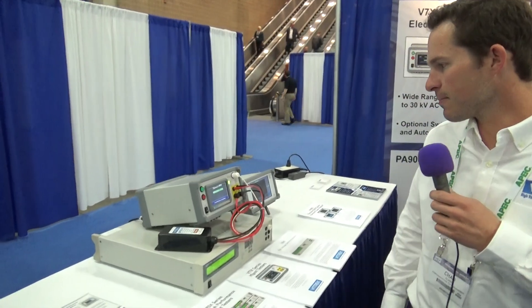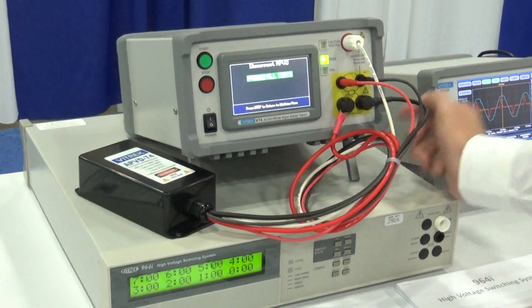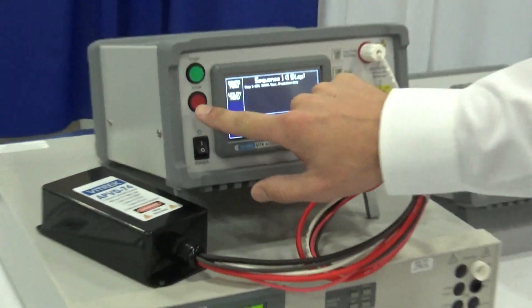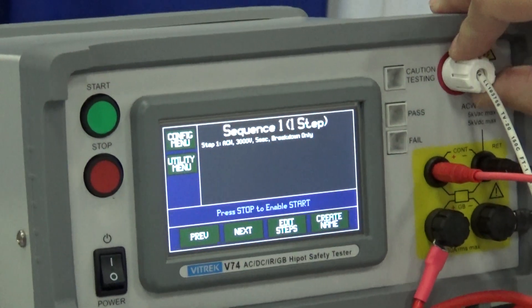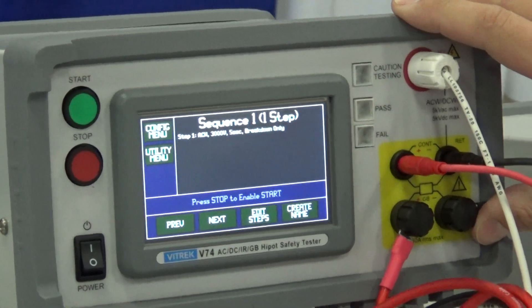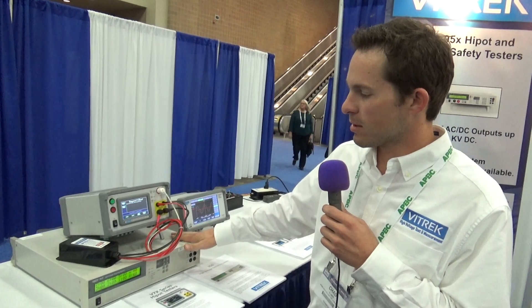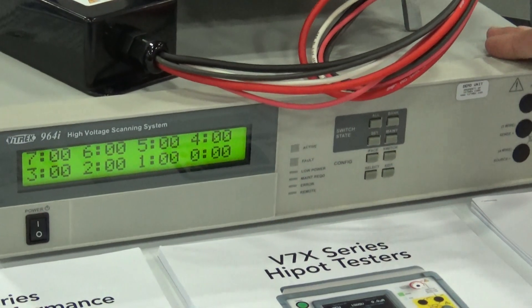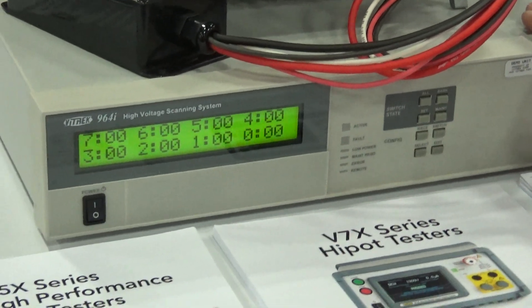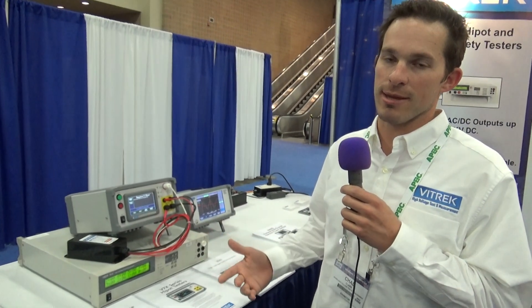Coming down the line here, this is one of our newer Hipot test series — it's the V7X series. This particular model is the V74. It does AC, DC high pot, insulation resistance, and ground bond. We have it paired with the 964 switcher, which helps expand the test capabilities. Almost limitless, but typically that's going to be in configurations of about 60 relays per chassis, and we can custom make that with the ratio you want of high voltage and return sides.